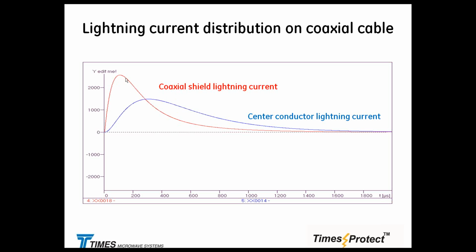So that's basically why we are using inline protectors on the RF coaxial cables. This is a 50 ohm system, but there is that but. And also you're going to see some propagation delay. So the differential current which is going to arrive at the equipment, if the impedance of the system is low, you're going to go through thermal runaway. You're going to burn everything with that current. If the system impedance is going to be very high, that differential current is going to become a flashover point. You're going to create a flashover voltage, and that's how we get destroyed.